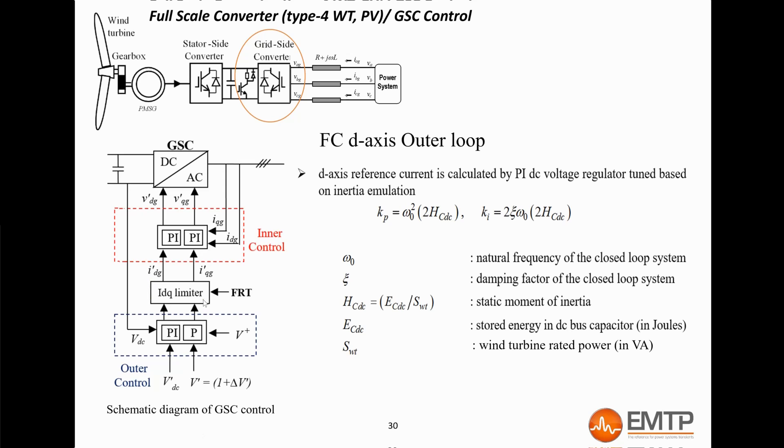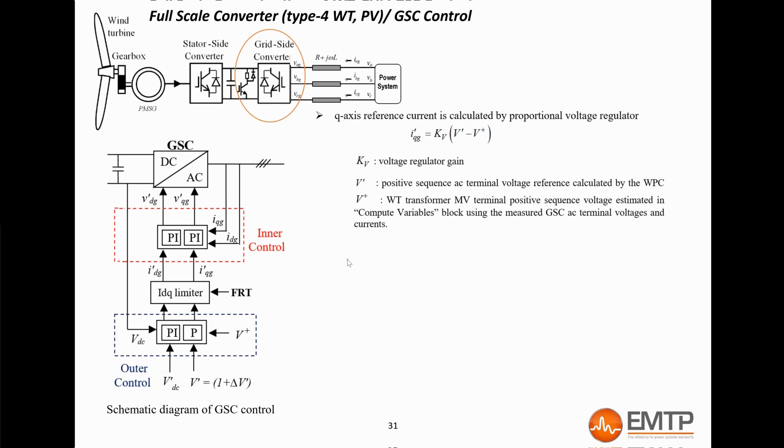The gains of the outer loop PI controller for the D-axis are calculated based on the DC bus capacitance. The equations used are explained here. The Q-axis loop now controls the Q-axis voltage in order to follow the reference sent by the PPC for the park reactive power control. The outer loop produces a Q-axis current reference, which is also limited, and sent to the inner loop, which commands the Q voltage reference. The outer loop here is a proportional controller where the gain is set by user in the mask.